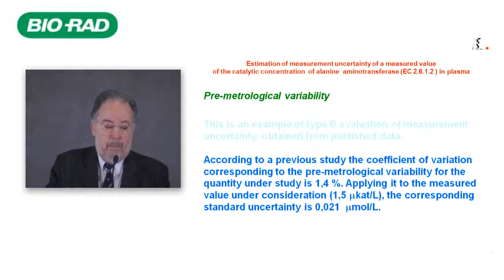The second factor of uncertainty is, in this case, and in almost practically all the cases when we need a calibration, the uncertainty of the calibration of the calibrator. This is also a type B uncertainty because the manufacturer has this information. If we need this information, it is a must for the manufacturer to give it. This information is generally not given with the package insert, but we must ask especially for this information, and the manufacturer always has it.